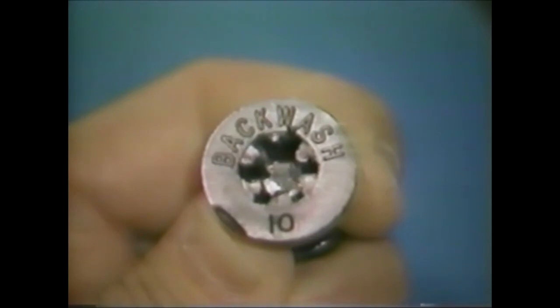The backwash control is coded with a number that corresponds to the resin tank diameter. Standard backwash controls are available for 6, 7, 8, 9, 10, and 12-inch diameter tanks.